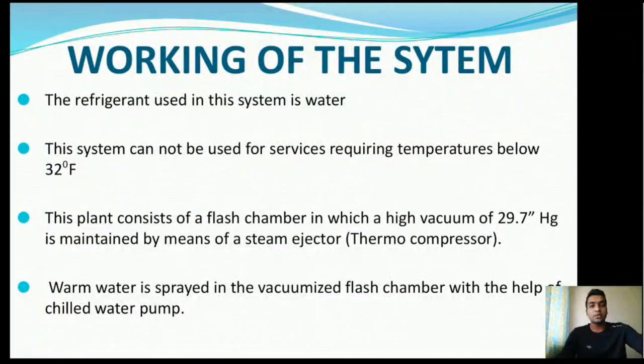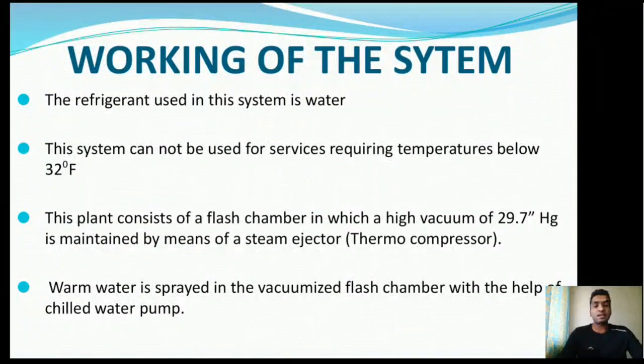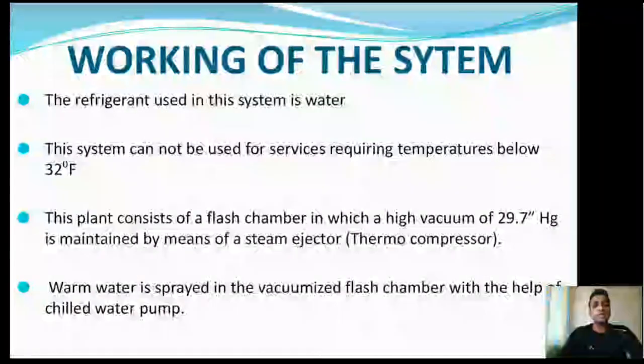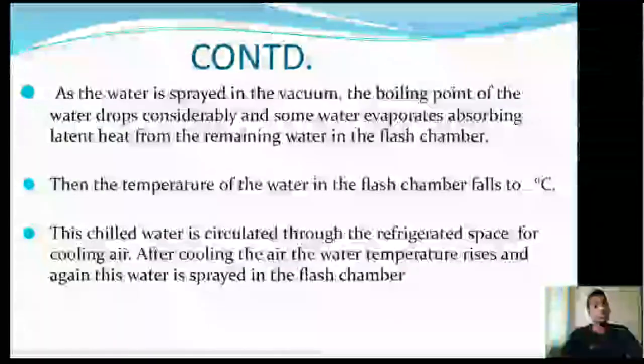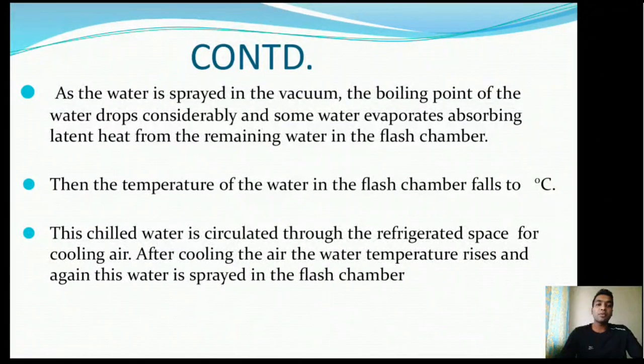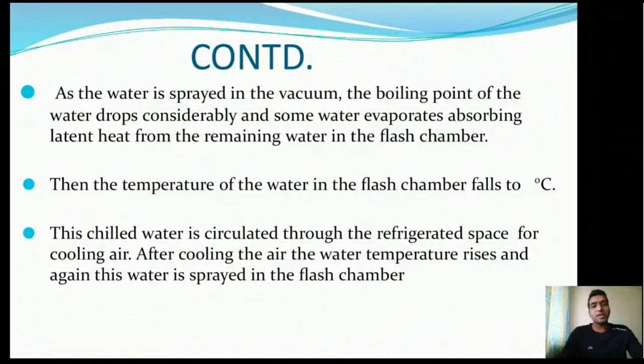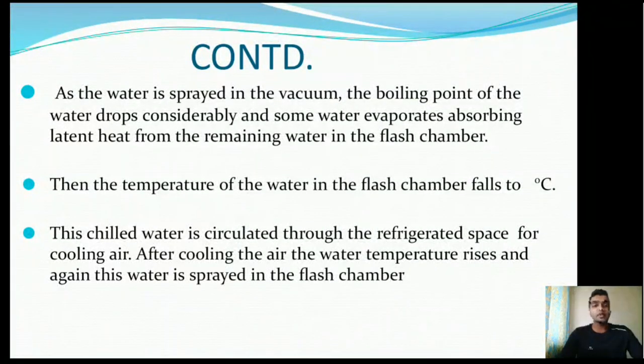After cooling the refrigerated space, the water temperature rises and this warm water is sent back to the flash chamber, and the cycle repeats. The refrigerant used is water, and the system cannot be used where temperatures below 0°C (32°F) are required. The flash chamber maintains a high vacuum of 29.7 inches by means of the steam ejector. Warm water is sprayed in the vacuumized chamber, its boiling point drops, some water evaporates absorbing latent heat from the remaining water, lowering its temperature. The chilled water circulates to the refrigerated space, and this is how the refrigeration effect is achieved.